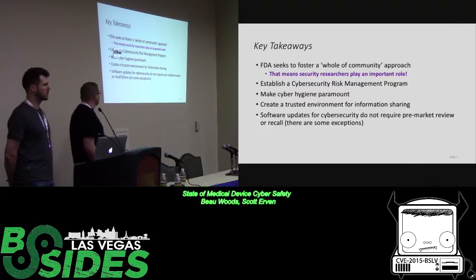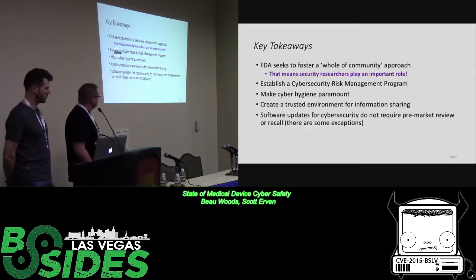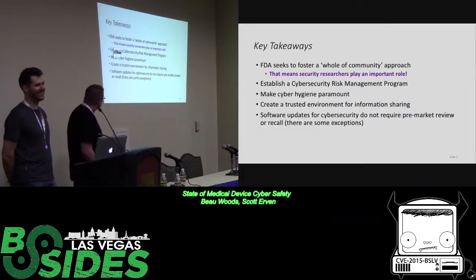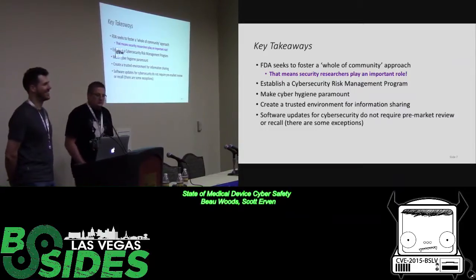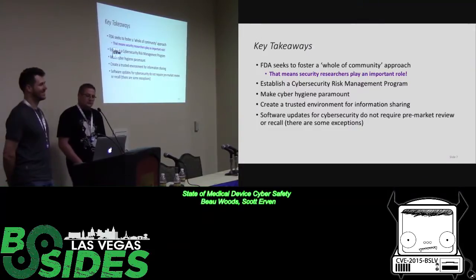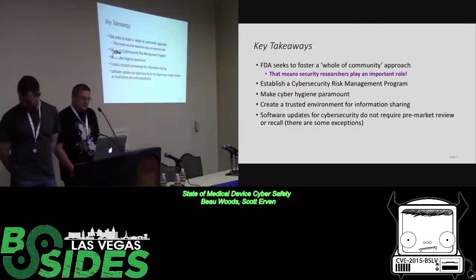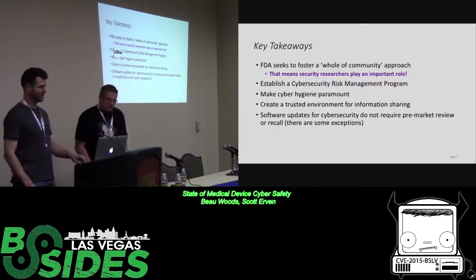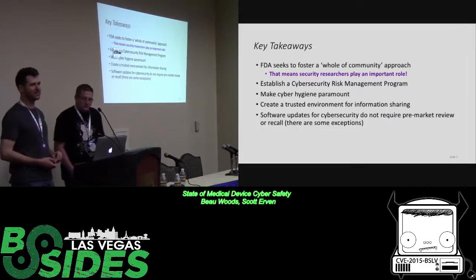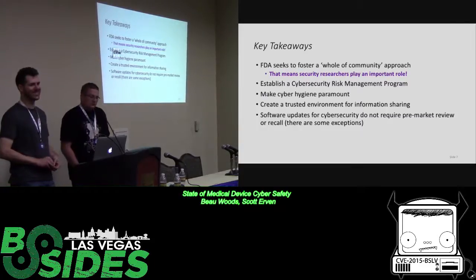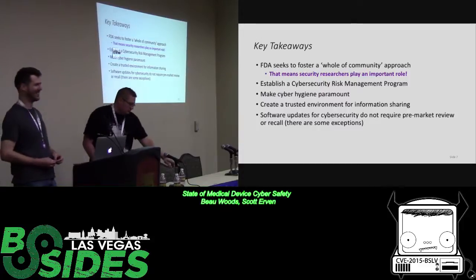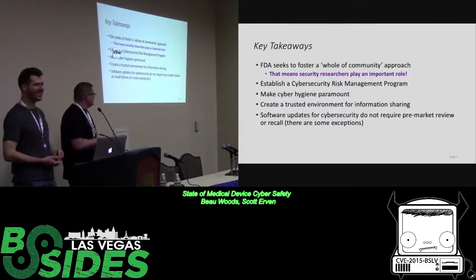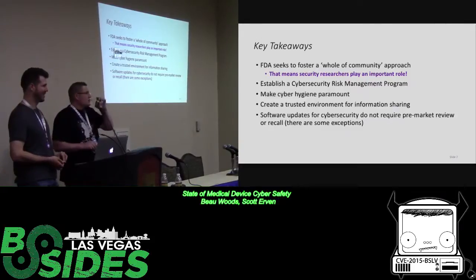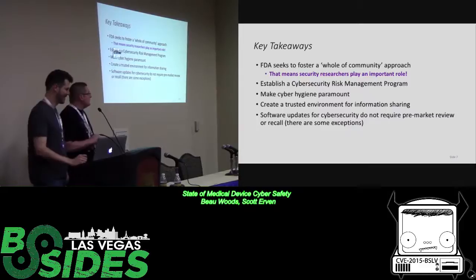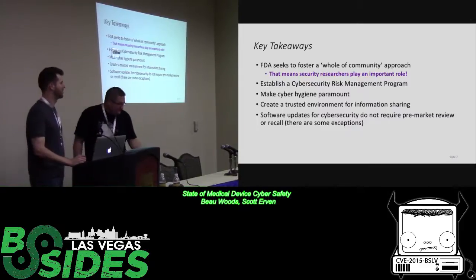And then the last point here is one of those myth-busting points that we like to talk about every time we have an opportunity to talk to audiences: in order to improve the cybersecurity posture of a medical device, software updates can be performed by the manufacturer without necessitating the manufacturer to come back to FDA with a new submission, with another pre-market application or pre-market 510(k) submission. It also does not necessitate, in most cases, a recall.